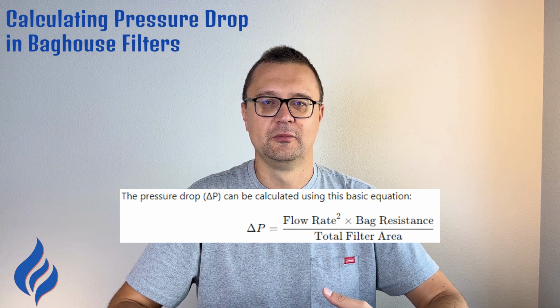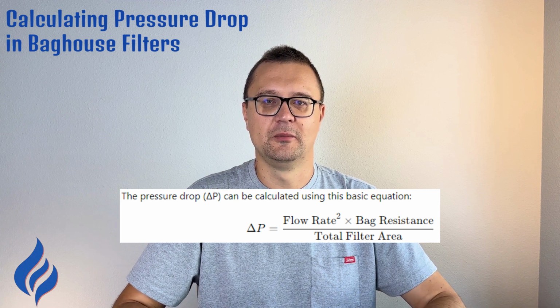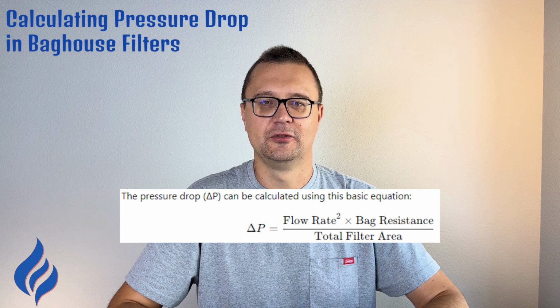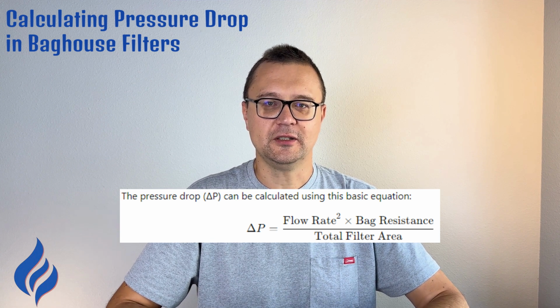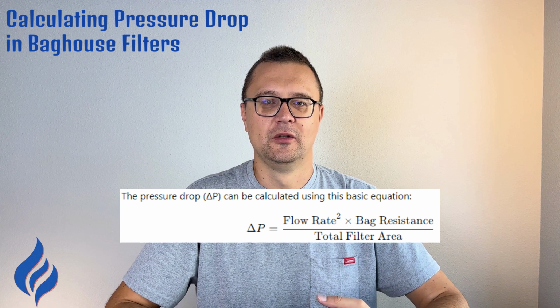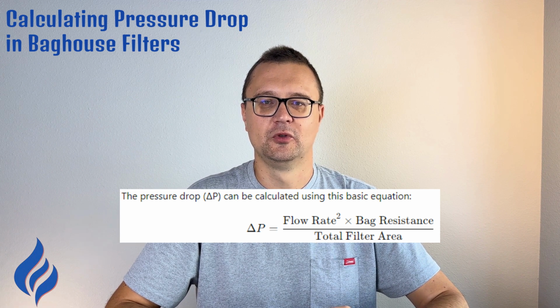Once you've calculated the pressure drop, compare it with the recommended range for your specific baghouse. If it's higher than expected, that's a sign of clogged filters or another issue. Too low? You might have leaks.